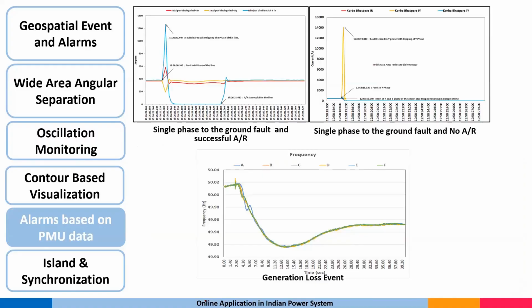We can have operation alarms. You can also see the faults happening in the system, and we immediately come to know whether the protection is operating correctly. Let us say there is a generation tripping, immediately the frequency drops. So this kind of generation loss event and fault event can be easily monitored in real time. And which phase the fault is on, and whether the protection has cleared the fault within the time duration or not. Because we are having 40 millisecond information and protection operates within 60 milliseconds, we easily come to know whether the fault has cleared within 100 milliseconds, 200 milliseconds or not. So this kind of information is also available now.